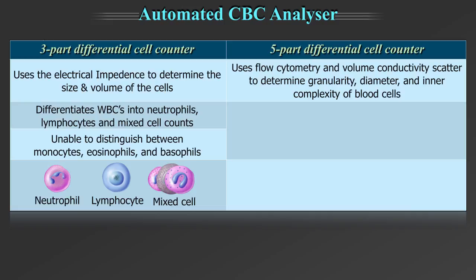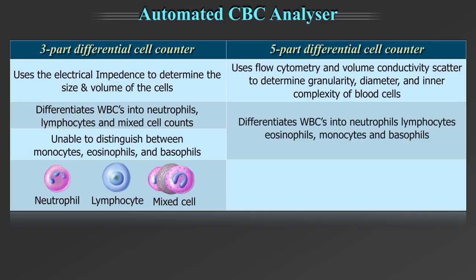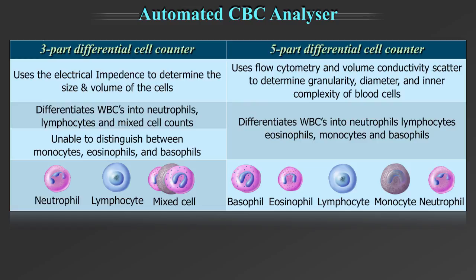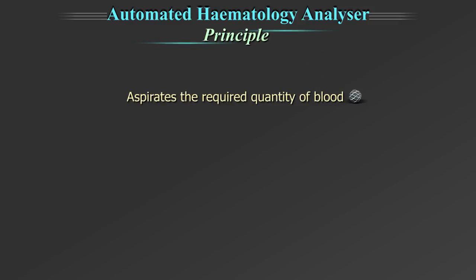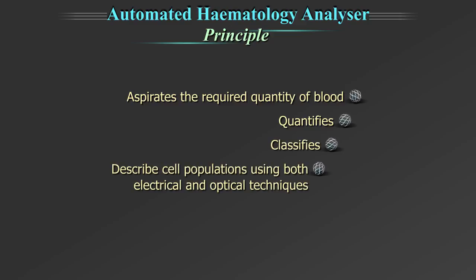The 5-part differential cell counter uses flow cytometry and volume conductivity scatter to determine the granularity, diameter, and inner complexity of blood cells. It differentiates white blood cells into neutrophils, lymphocytes, eosinophils, monocytes, and basophils. The automated CBC Analyzer aspirates the required quantity of blood, quantifies, classifies, and describes the cell population using both electrical and optical techniques.